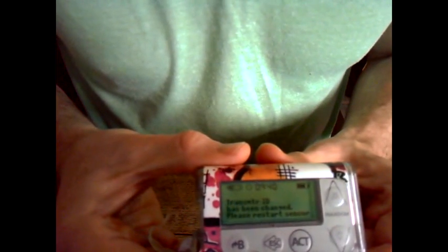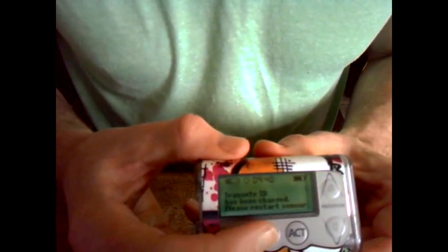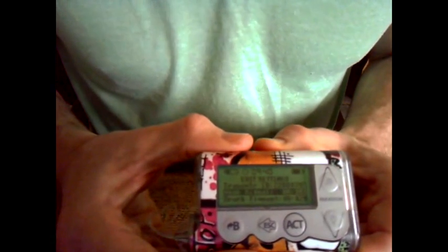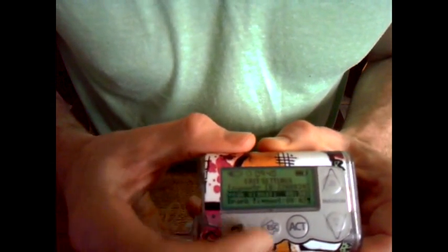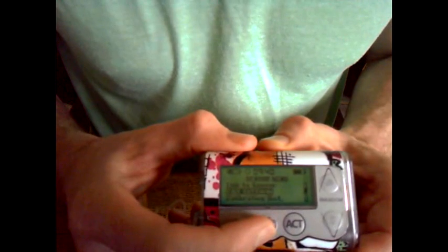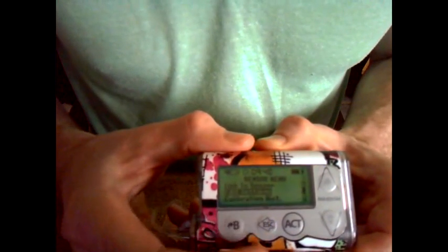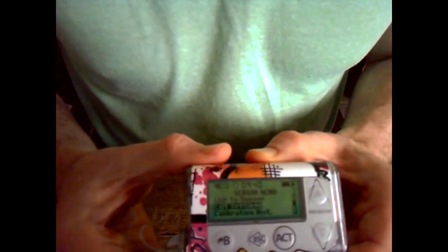Once you press Act there, it knows that the transmitter ID has been changed, so it wants to restart the sensor. So you can just press Escape there, and then that will take you back into your menu. Press Escape again, and then you're now in your sensor menu, and what you're going to do is link to the sensor.